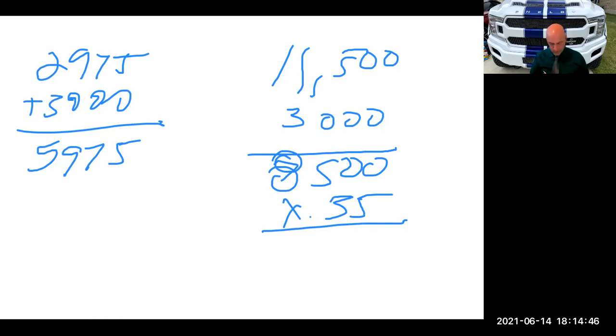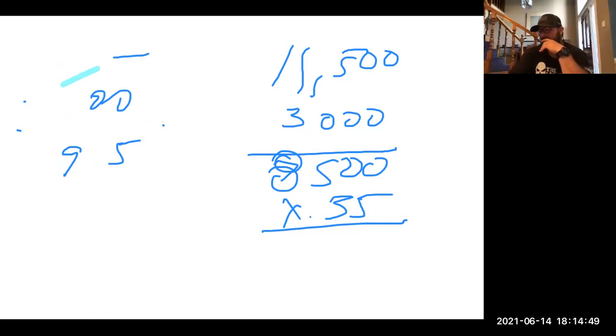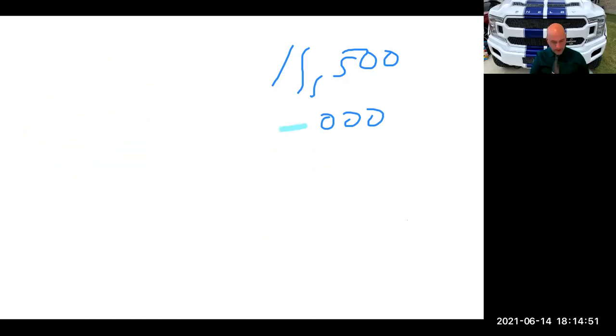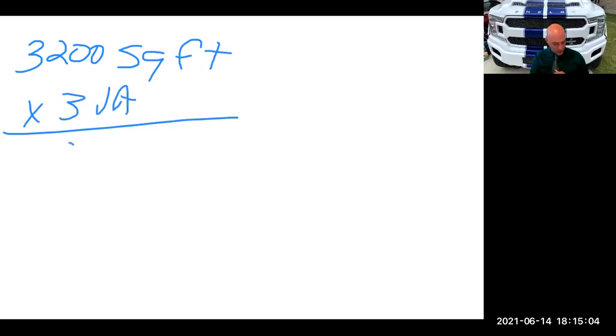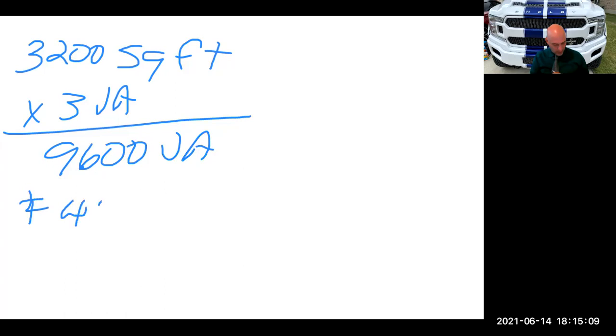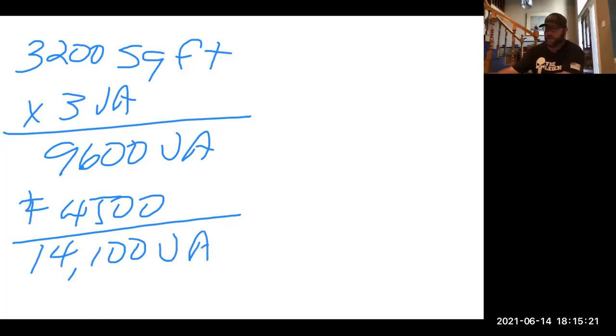So let me, excuse me. Oh yeah, how did I miss that? I'm telling you what, I don't know. It's been rough on everybody. 3,200 square feet, let's try this again. Times 3 VA is going to give us the 9,600, which is what we had before, plus the 4,500. I must have forgotten to add those two together, or no, I added them together. I just goofed and put 11 instead of what this would have been, which would be 14,100 VA. Yeah, there we go.